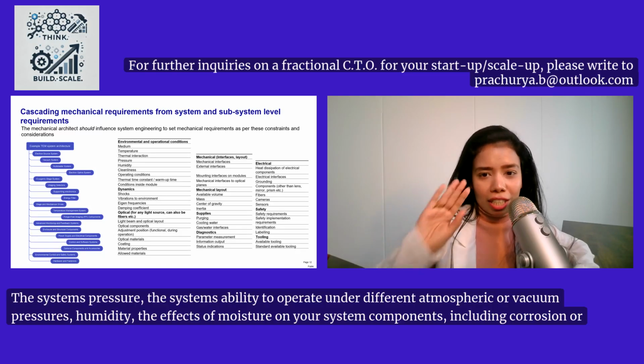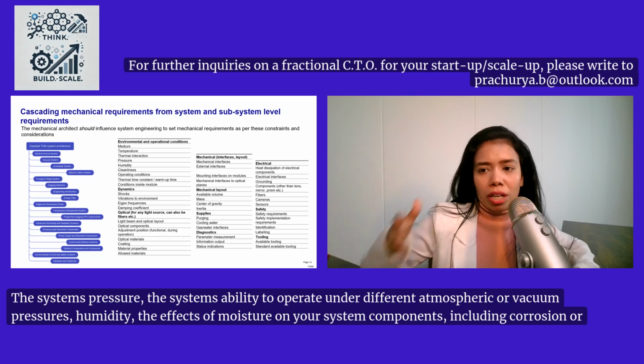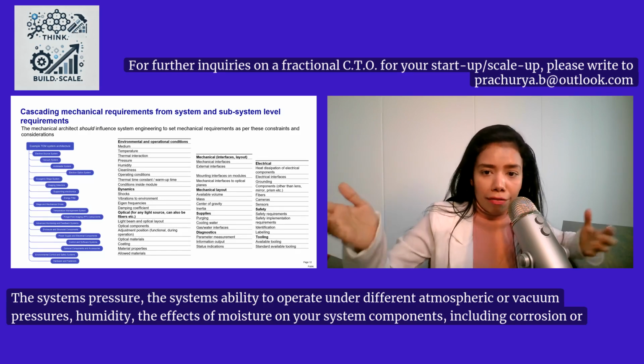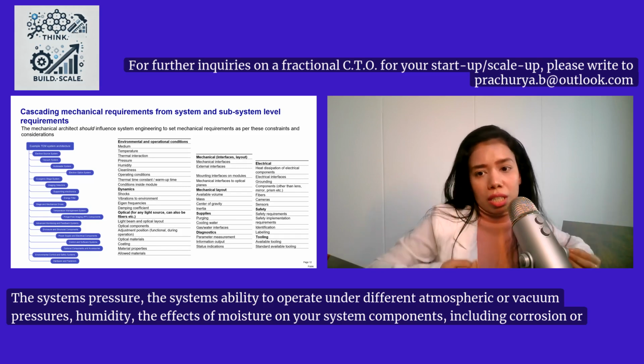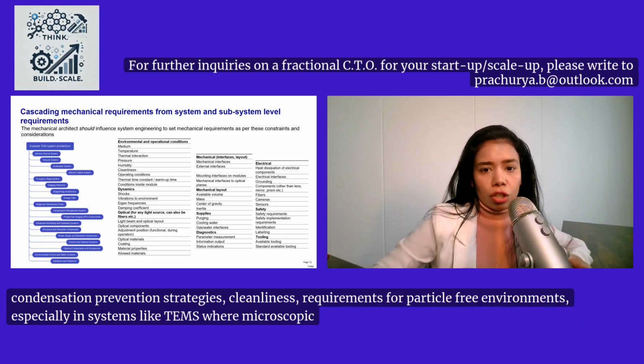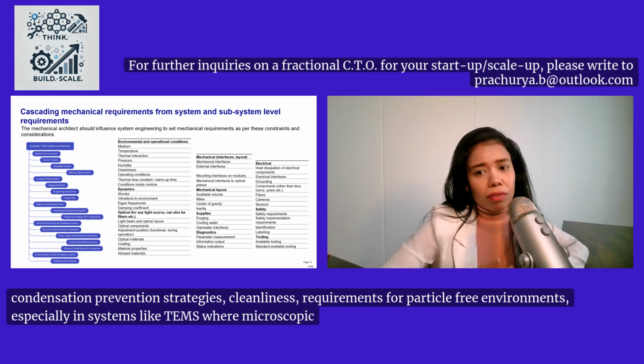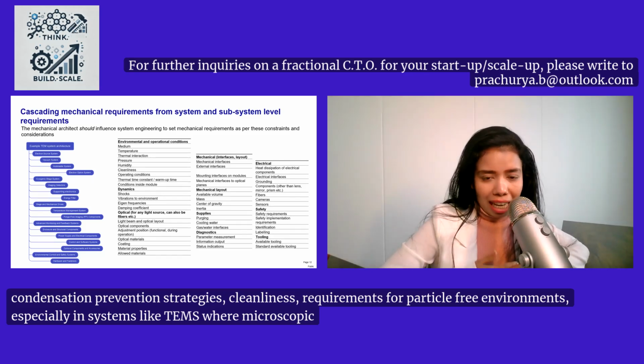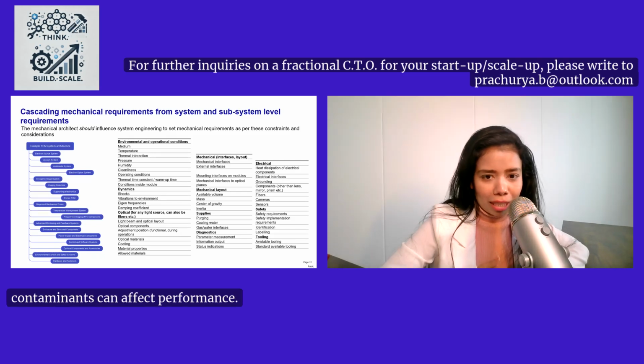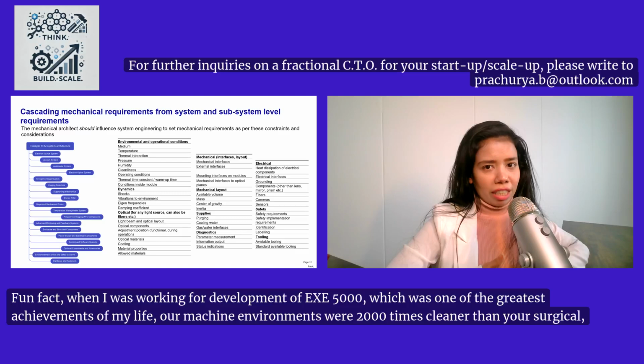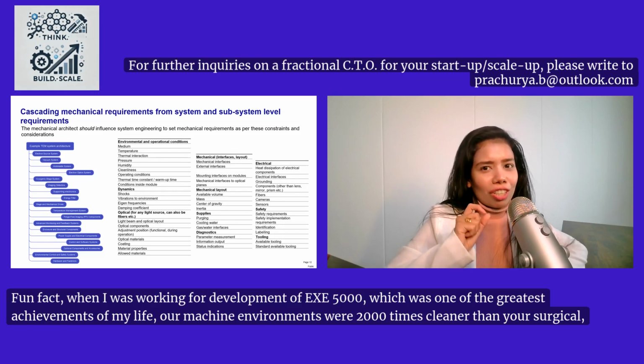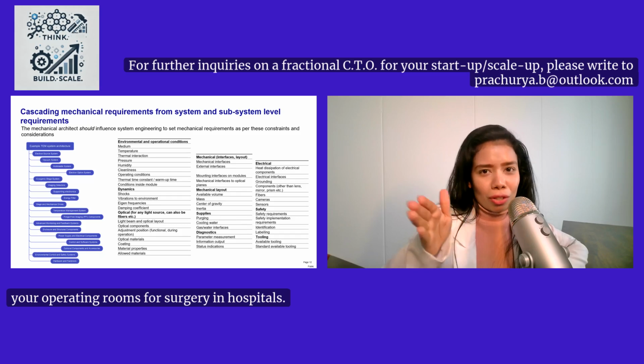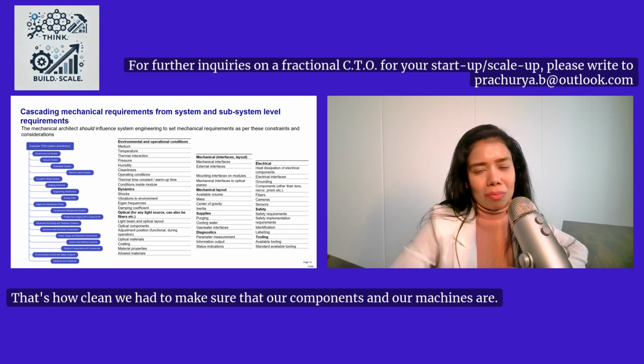The system's pressure, the system's ability to operate under different atmospheric or vacuum pressures, humidity, the effects of moisture on your system components, including corrosion or condensation prevention strategies, requirements for particle-free environments, especially in systems like TEMs, where microscopic contaminants can affect performance. Fun fact, when I was working on the development of EXE 5000, which was one of the greatest achievements of my life, our machine environments were 2,000 times cleaner than your operating rooms for surgery in hospitals. That's how clean we had to make sure that our components and our machines are.